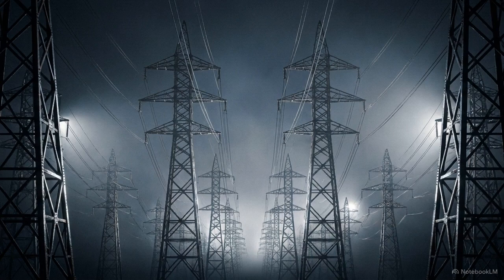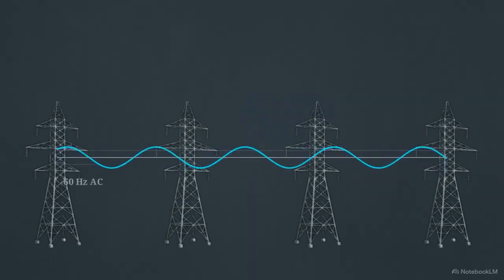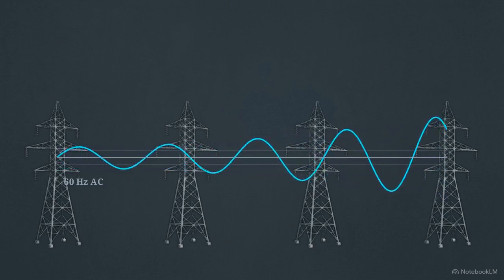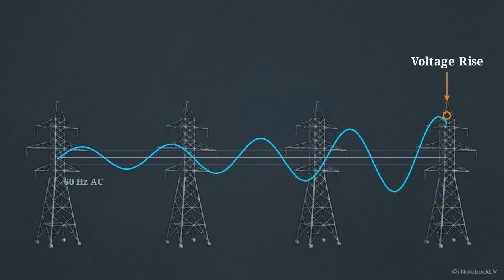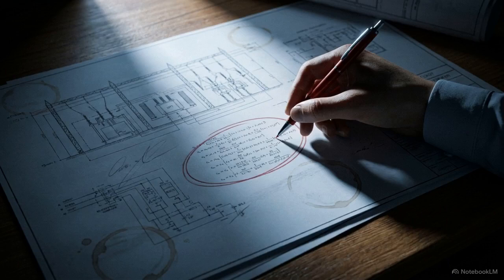We normally think of the power grid as a highly predictable machine governed by clean math. We've seen how phenomena like the Ferranti effect, where voltage rises at the end of a long, lightly loaded transmission line, follow strict, manageable rules of physics. But under specific conditions, those equations lose their predictive power. The clean 60 Hz sine wave starts warping into a non-periodic, erratic surge that follows different, nonlinear rules. Engineers call this phenomenon ferroresonance.